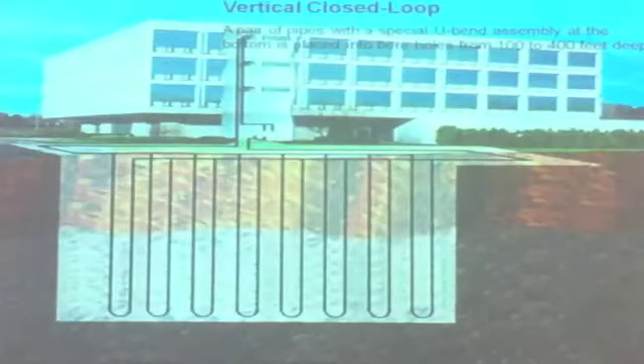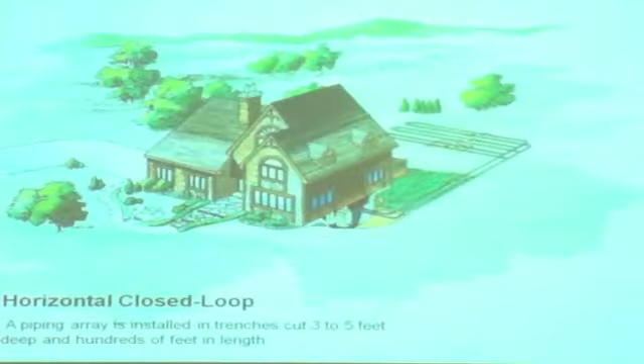So typical vertical geothermal heat exchangers, you got the vertical, which we would do in most of our houses in Houston. Most of the office buildings will do this. Keep going. Horizontal loops, if you've got a rural community or you got a whole bunch of land, it takes about 3 times the land area to do a horizontal loop as it does a vertical loop. And for most areas of Houston, because our drilling is relatively cheap, what it costs you to do a horizontal loop with a backhoe, if you have to pay for somebody, you can almost get it drilled for the same price and have a whole lot less exposure to the land. Keep going.